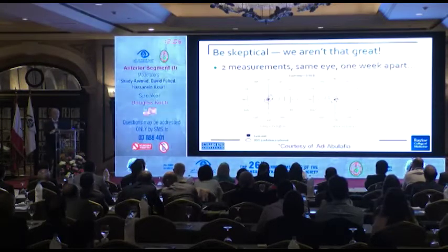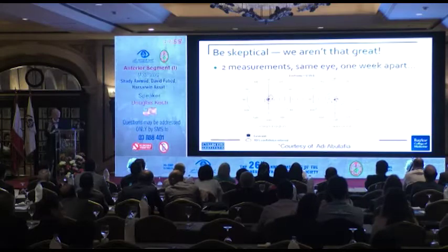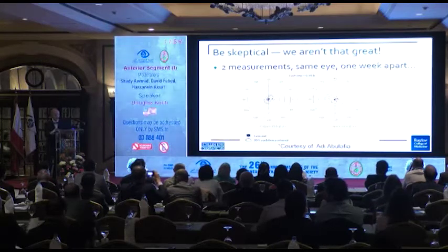But we really don't do as well as we think we do. These are measurements of a group of patients taken 1 week and then 1 week later. So same eye, same patient, taken 1 week later. This is the first device that was done. And you can see the cluster, these are the differences in the measurements. That's fairly tight.